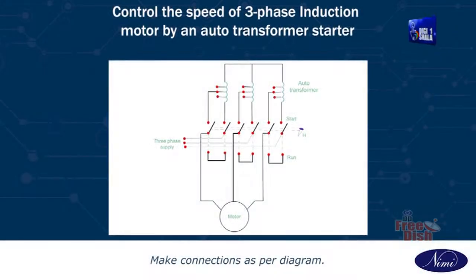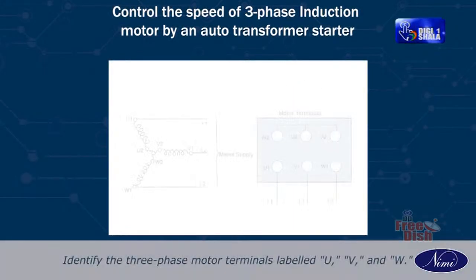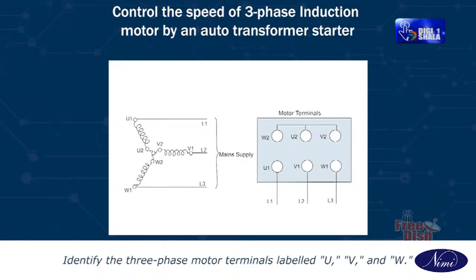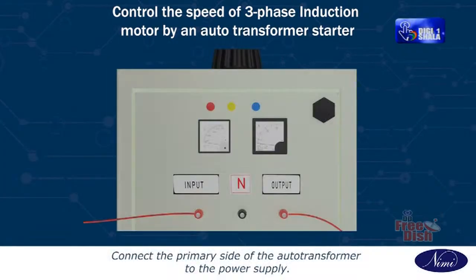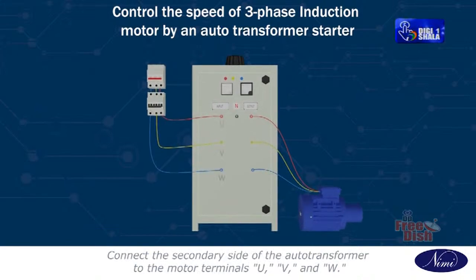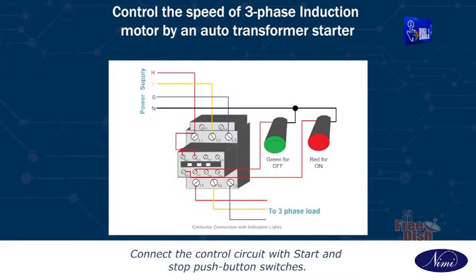Make connections as per diagram. Identify the three-phase motor terminals labeled U, V and W. Connect the primary side of the auto transformer to the power supply. Connect the secondary side of the auto transformer to the motor terminals U, V and W. Connect the control circuit with start and stop push button switches.